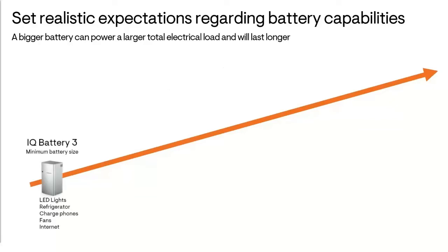While the Enphase IQ batteries start at just 3.3 kilowatt hours, this size is not going to be sufficient for most homeowners. This small battery size should only be used in conjunction with an essential load subpanel and just a few small loads, as well as Enphase load control to improve system resilience.